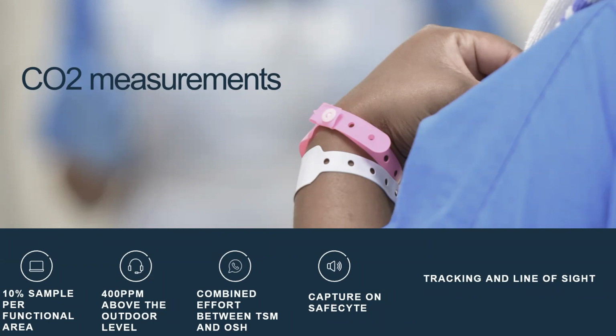We are doing a sample rate in the functional areas of 10%. The requirement is that the carbon dioxide level cannot be more than 400 parts per million above the outdoor carbon dioxide level. So Shireen will now talk into that when she presents the centralization and upload of that.